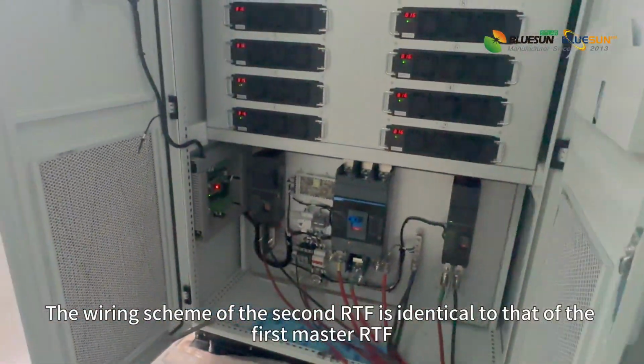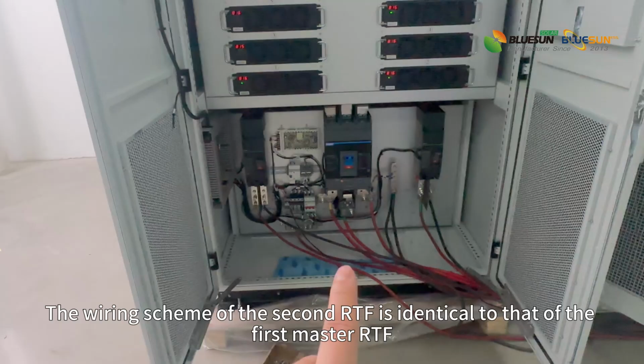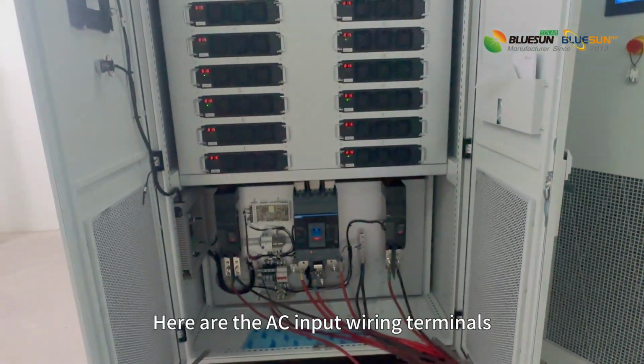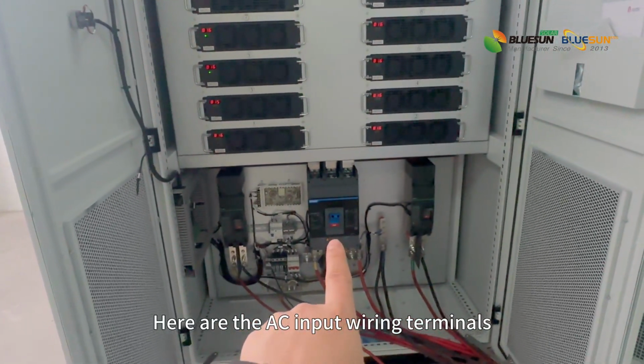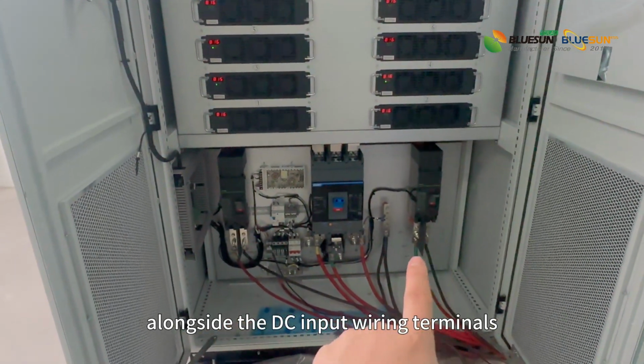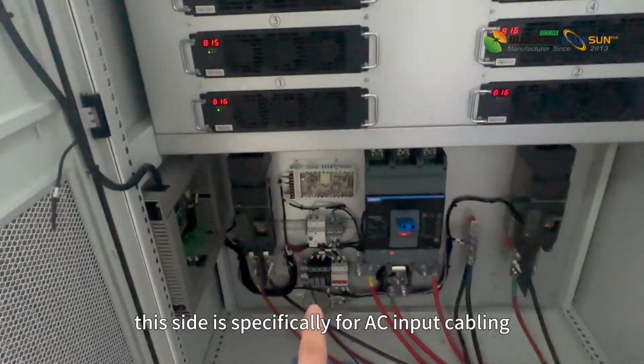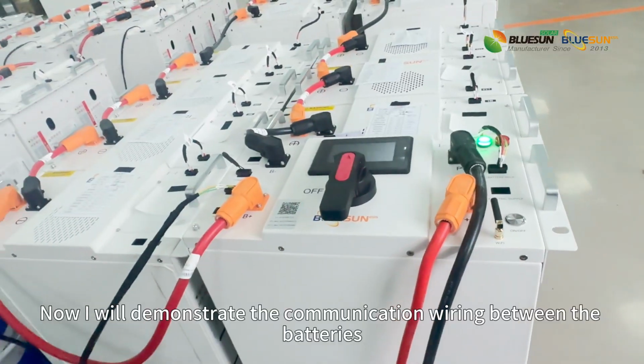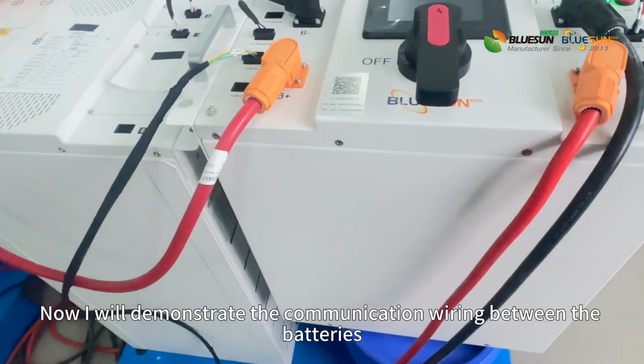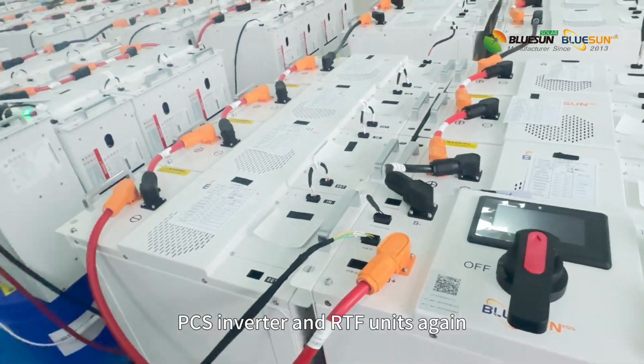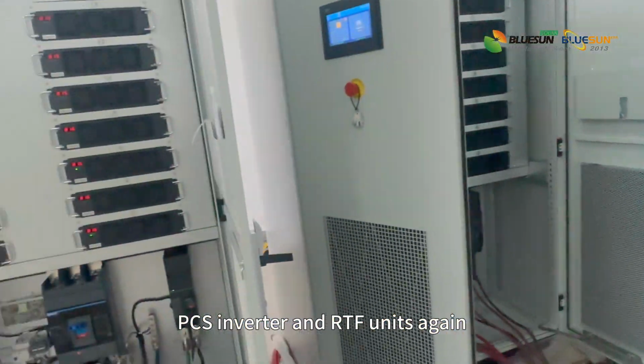The wiring scheme of the second RTF is identical to that of the first master RTF. Here are the AC input wiring terminals, alongside the DC input wiring terminals. This side is specifically for AC input cabling. Now I will demonstrate the communication wiring between the batteries, PCS inverter, and RTF units again.